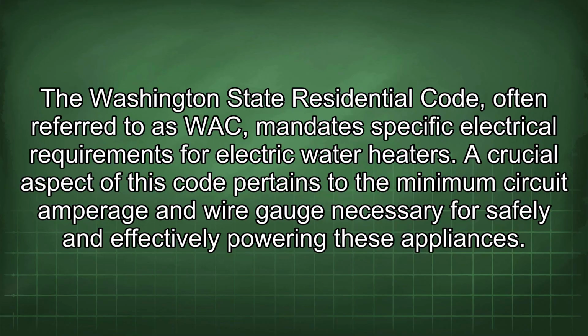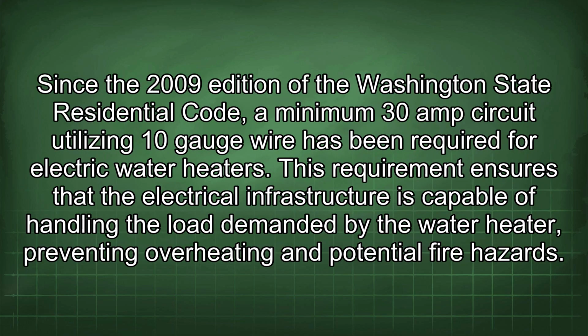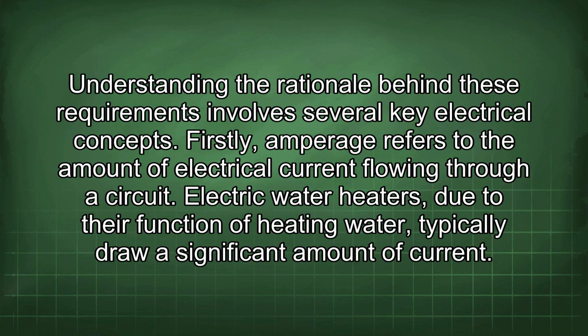The Washington State Residential Code, often referred to as WAC, mandates specific electrical requirements for electric water heaters. A crucial aspect of this code pertains to the minimum circuit amperage and wire gauge necessary for safely and effectively powering these appliances. Since the 2009 edition of the Washington State Residential Code, a minimum 30-amp circuit utilizing 10-gauge wire has been required for electric water heaters. This requirement ensures that the electrical infrastructure is capable of handling the load demanded by the water heater, preventing overheating and potential fire hazards. Understanding the rationale behind these requirements involves several key electrical concepts.